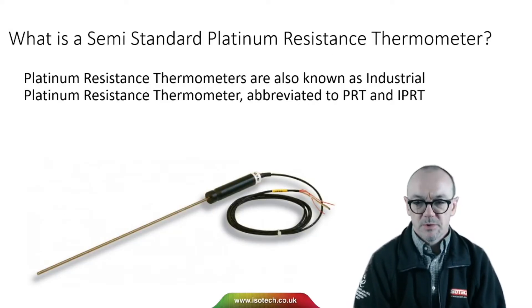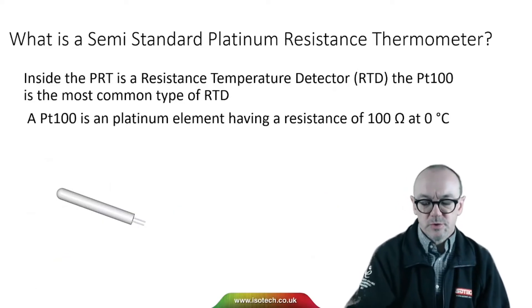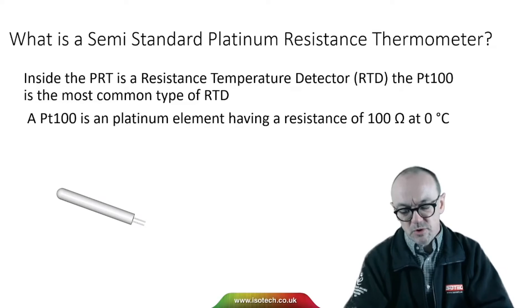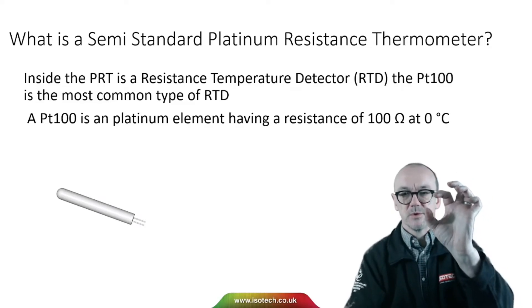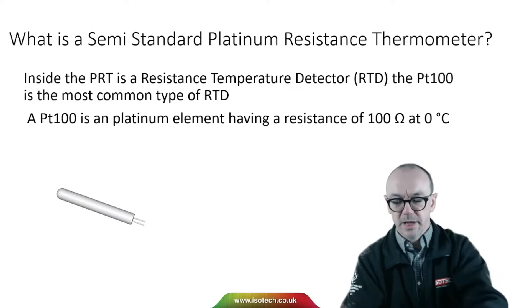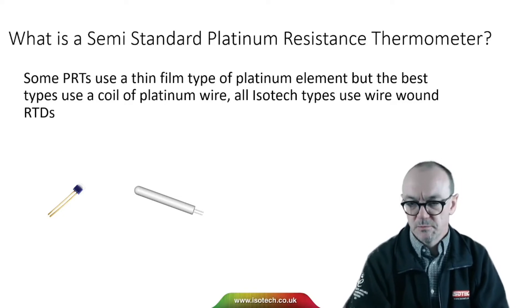The platinum resistance thermometer, also known as industrial platinum resistance thermometers, is often abbreviated to PRT or IPRT. Inside the PRT is a resistance temperature detector. The PT100 is the most common type — a device with a resistance of 100 ohms at 0 degrees C. Some PRTs use a thin film of platinum rather than a coil of wire, but the best types use a coil. The standard has better tolerances for the wound types, and all Isotech thermometers use wire wound RTDs.